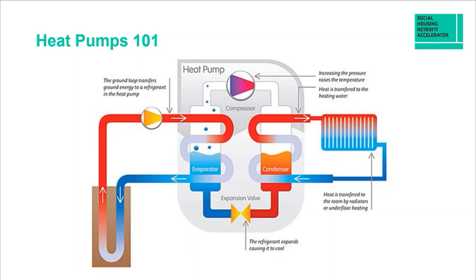In the condenser — the second heat exchanger — we transfer the thermal energy into the household systems: radiators, underfloor heating, or a hot water cylinder. This cools the refrigerant. Then at the bottom we take the pressure off in the expansion valve and the refrigerant returns to a liquid state — a continuous cycle. The compressor runs when the house is calling for energy, and stops when there's no demand.